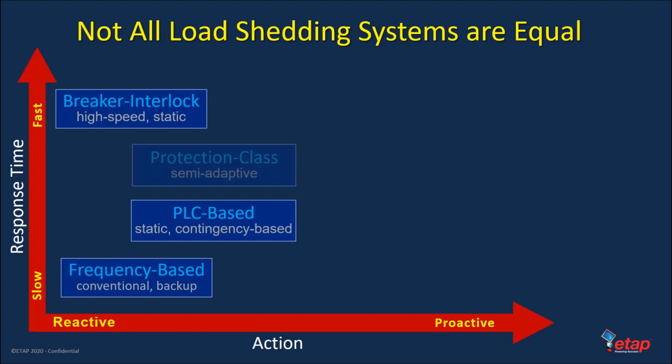to be dropped. A protection class load shedding controller offers advantages over the PLC-based scheme, such as the use of a distributed network via a power management system, as well as an automated means of load relief. However, in such applications, monitoring of the power system is limited to a portion that is monitored with scattered information. This drawback is further compounded by the implementation of predefined load priority tables that are performed sequentially to curtail blocks of load regardless of dynamic changes in the system, loading, generation, or operating configuration.